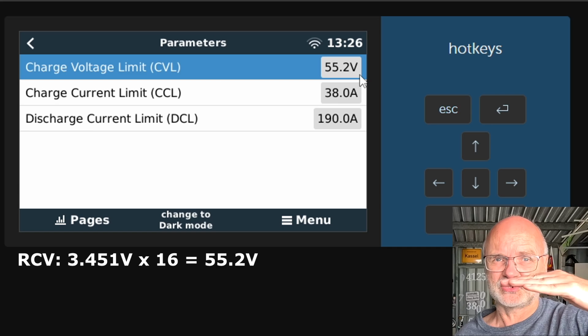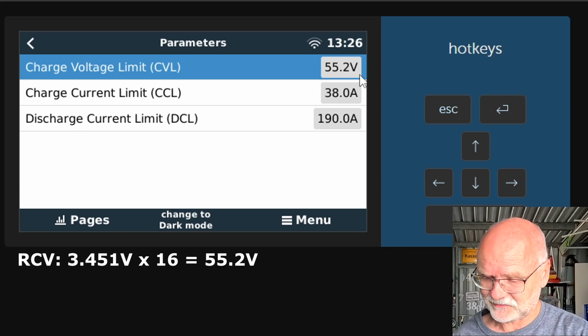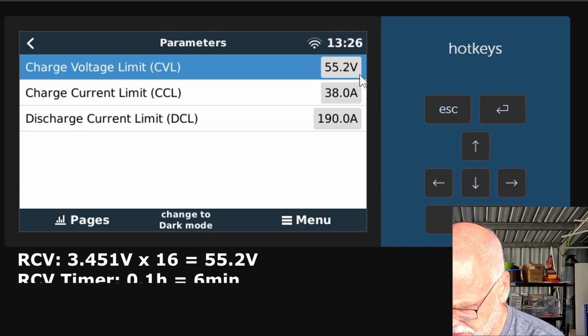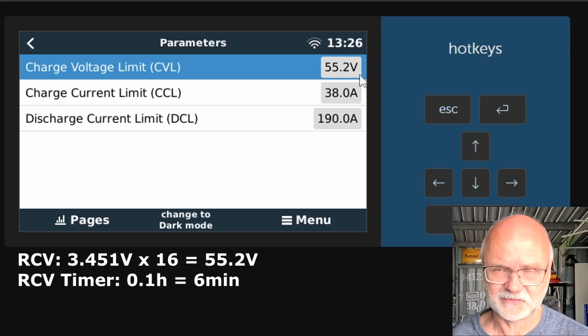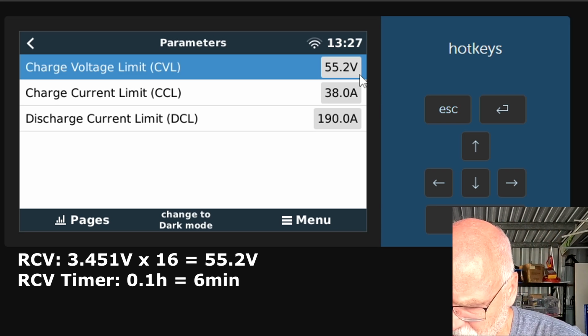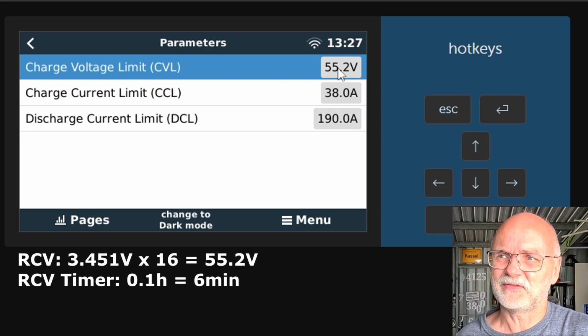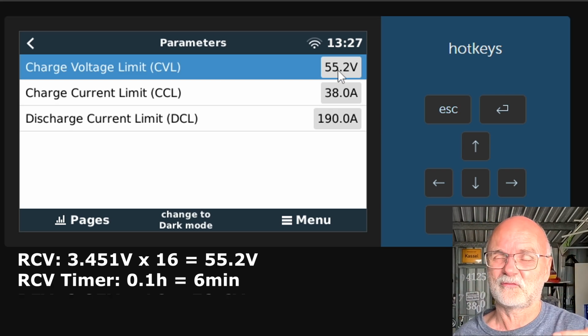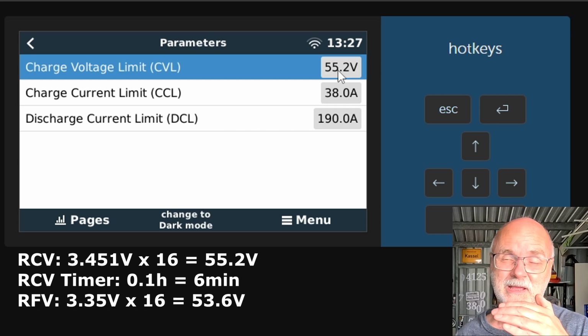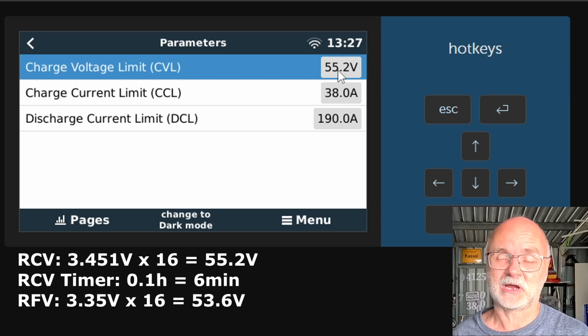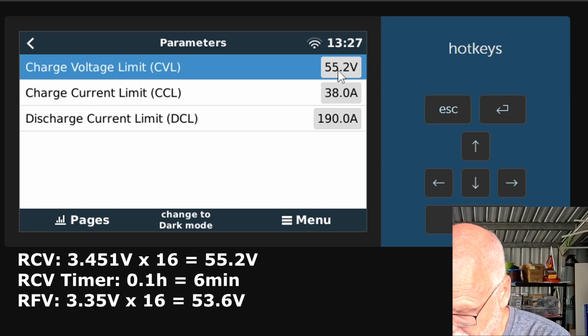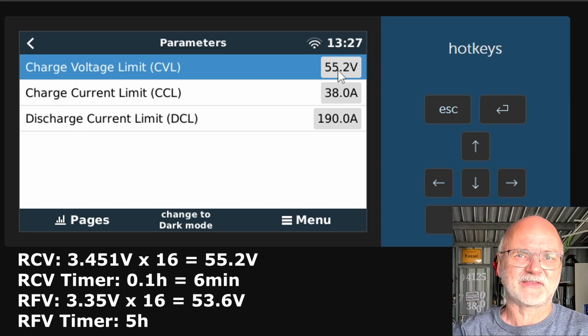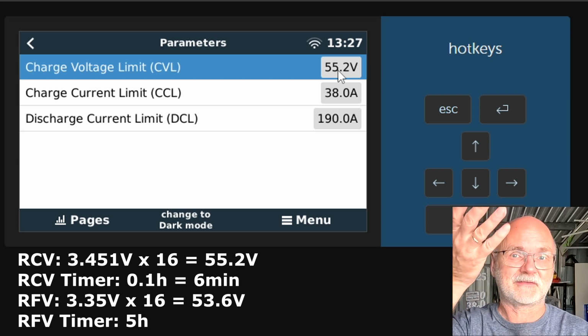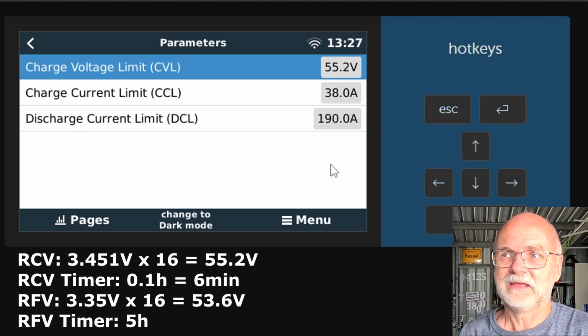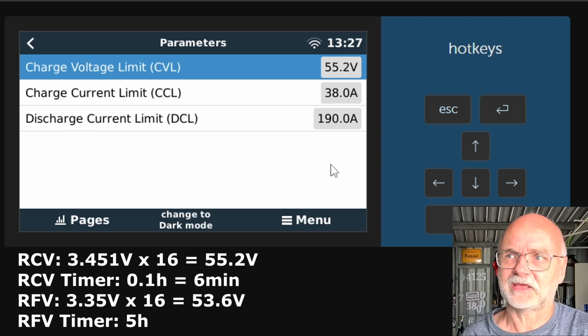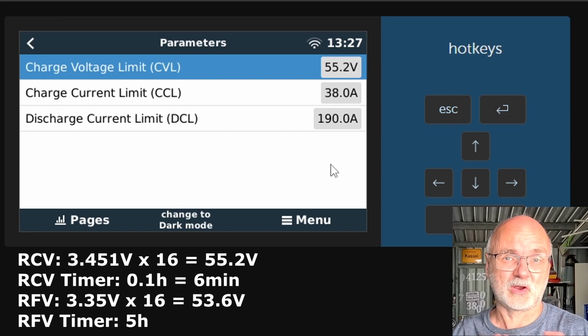So we are holding this voltage constantly for the set timer in the BMS, which is 0.1 hours, so 6 minutes. In about 4 minutes now we should see this value actually dropping to 53.6, and this is what the BMS then requests from the solar charge controller, and this will stay for the next 5 hours, basically after sunset, and then it resets and rebulks to 55.2 volts again. This is the whole charging cycle the JK BMS can do, and this has always worked absolutely fine.